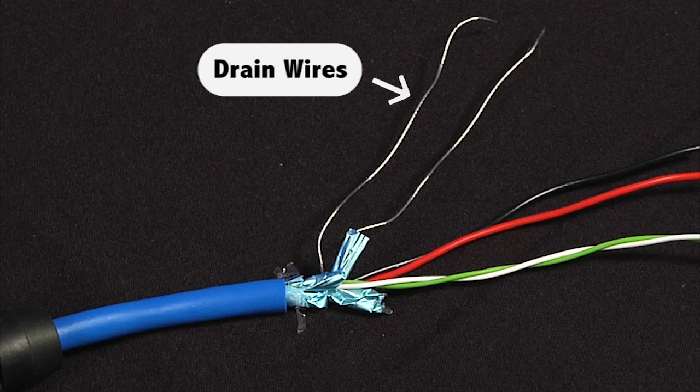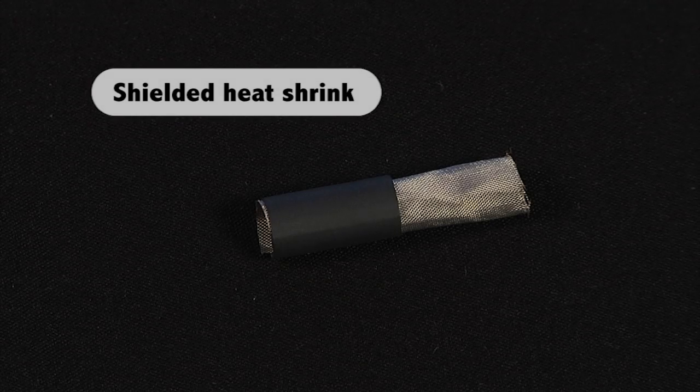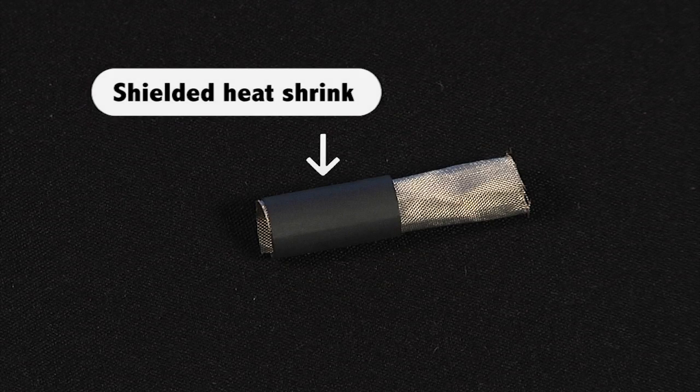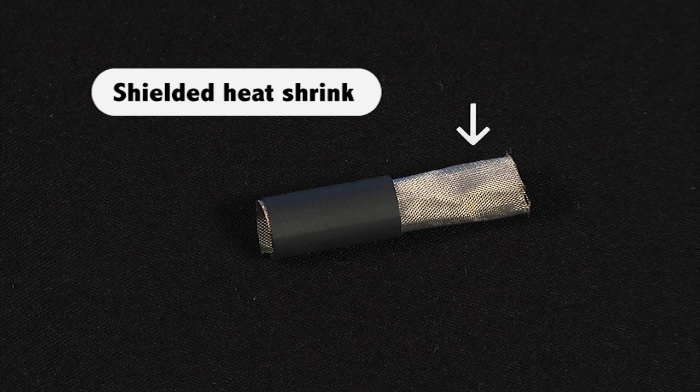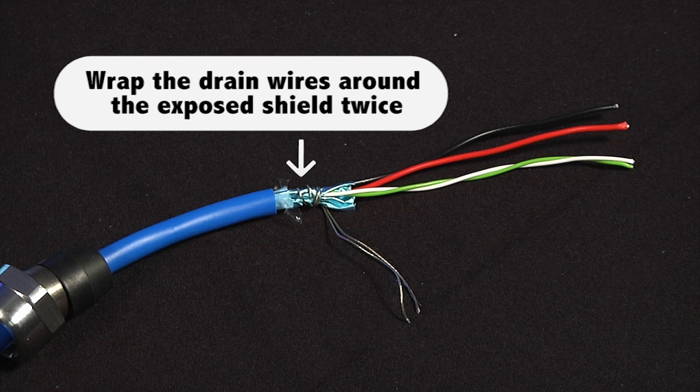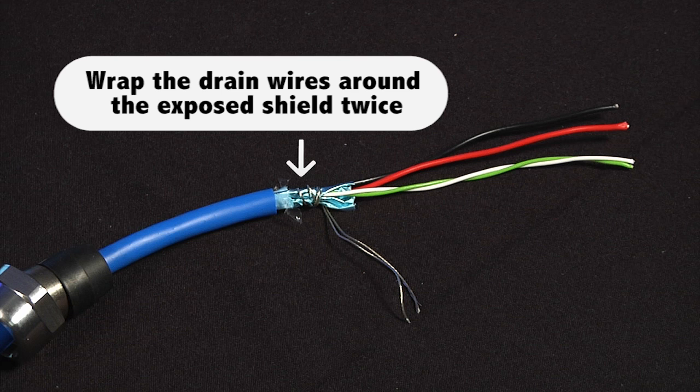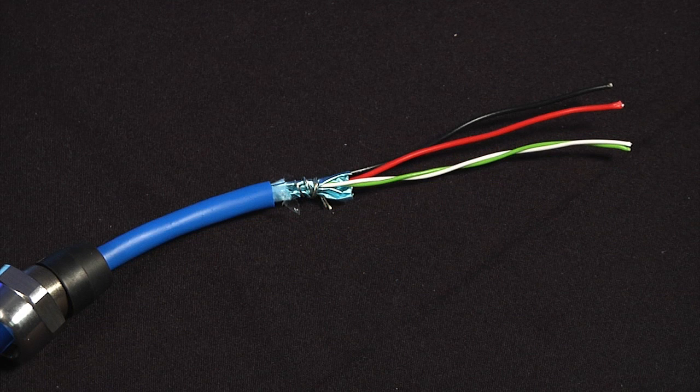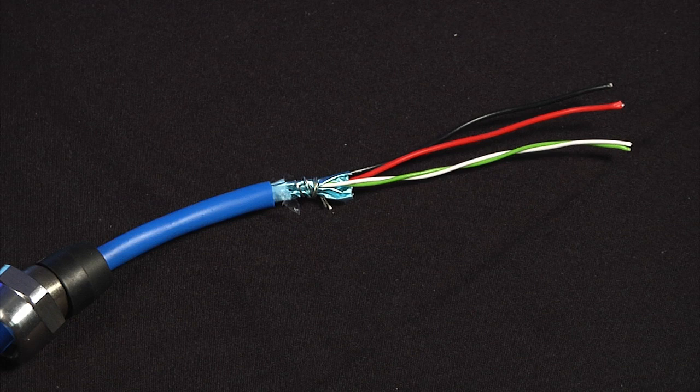With shielded cable, the next step is to apply a short piece of shielded heat shrink in order to make sure the drain wires are properly terminated inside the gland. Shielded heat shrink has about an inch of heat shrink tubing on one side and an inch of exposed shield on the other. Before attaching the heat shrink, wrap the drain wires around the exposed shield twice. Cut off any excess length of wire once you do this.